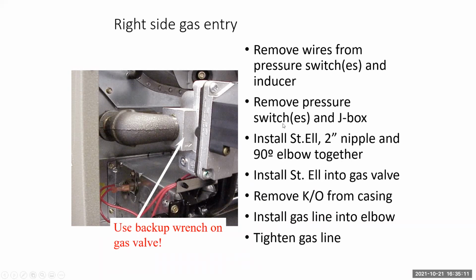I'm going to leave this up for a minute so you guys can take a screenshot of it. Just showing your 2-inch nipple off your elbow. But take a picture of this so you have it. As long as you do it as I specify here, there will be enough room to get your J box, your pressure switches, and everything mounted back up properly, no problems. So I'll leave this up for a second. Big things here: street ell off the gas valve with a 2-inch nipple on the backside of that into a tight 90. And then you're off and running back to the right.